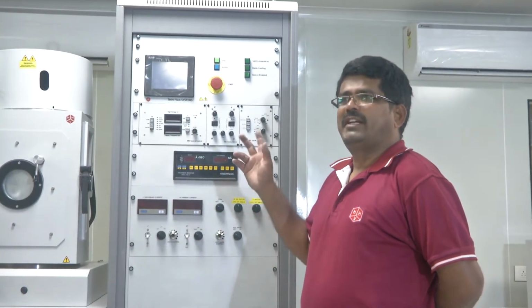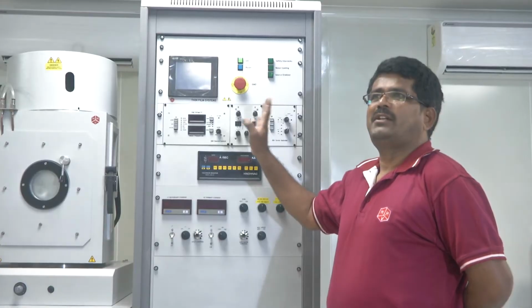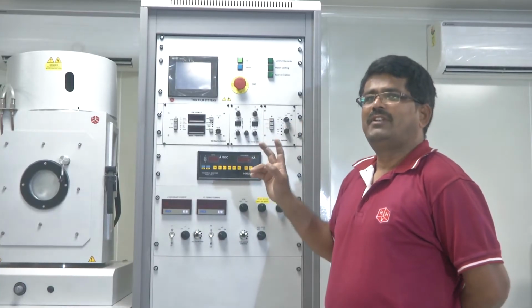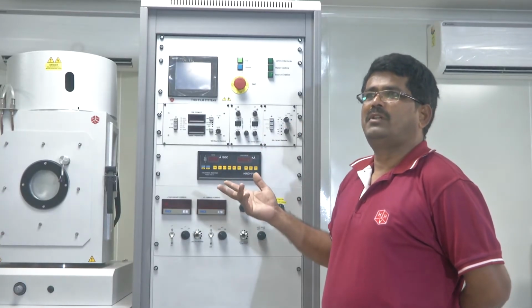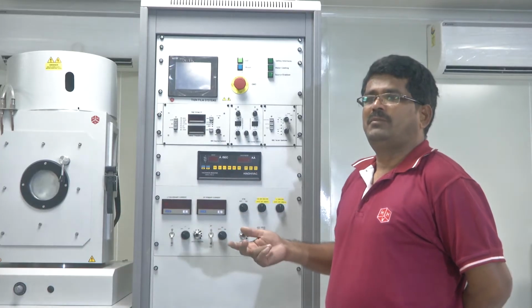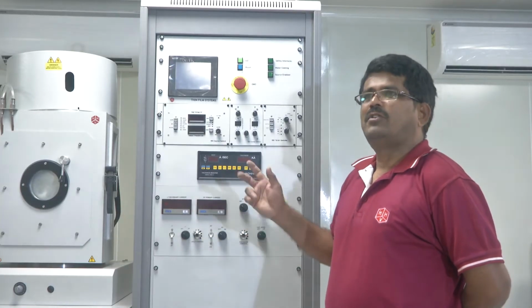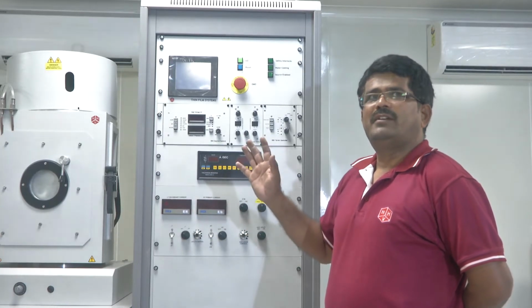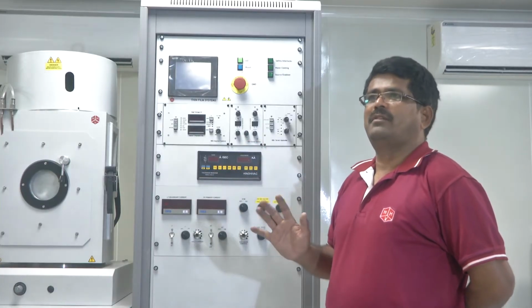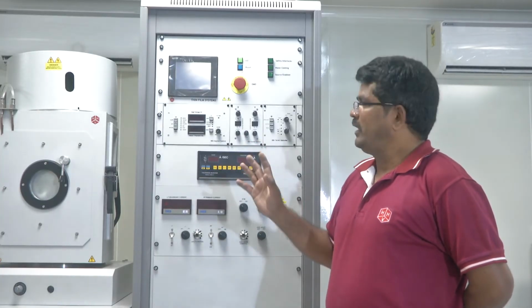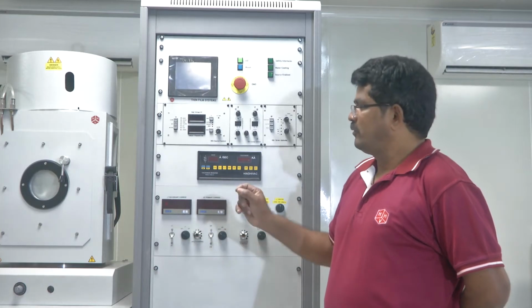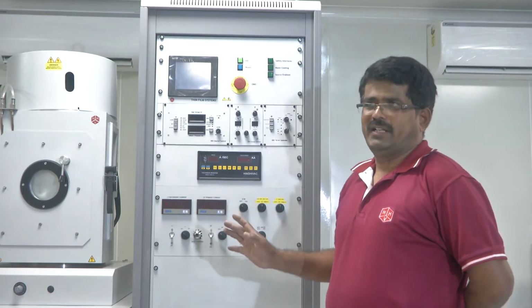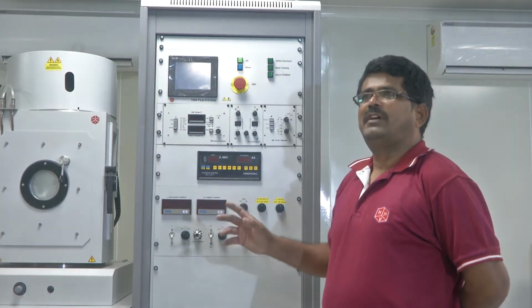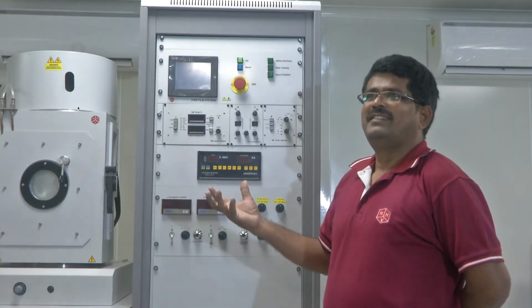After the turbo is getting ready, the turbo ready indication comes. After that, switch on the turbo roughing valve. Wait until -2 millibar. Then go to high vacuum. Wait until you reach -6. You will require base vacuum. After reaching base vacuum of -6, you can go for ion bombardment cleaning. You need ion bombardment for cleaning your substrate.